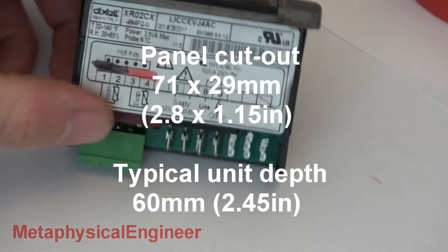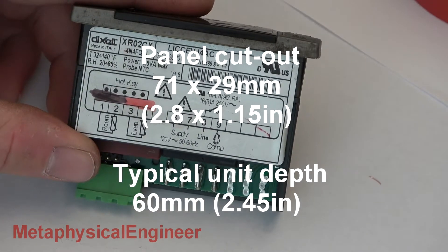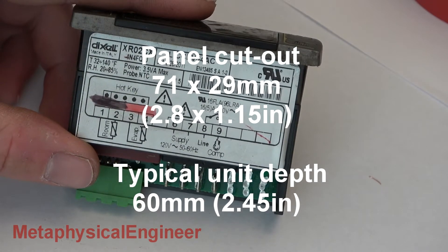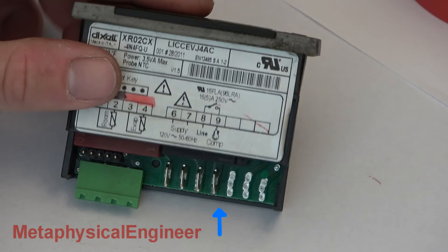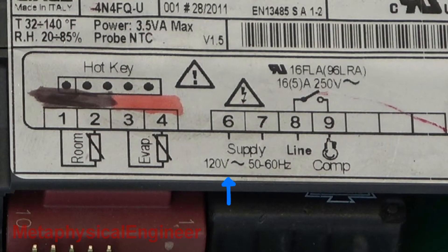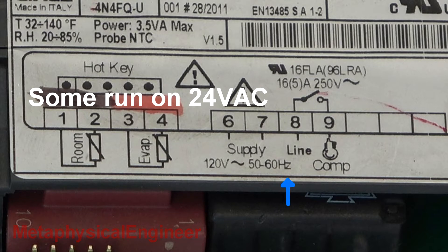They share a similar form factor with differences in overall length as well as number and type of connections and control capability. This one uses spade terminals for the line voltage and screw clamp terminals for the thermistors and low voltage. It's rated for 120 volt single phase supply, though 208, 230 and even dual voltage versions are available.